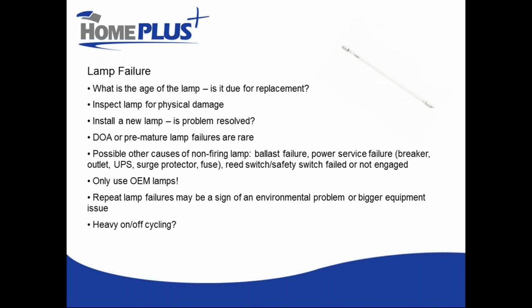Repeated lamp failures could also be a sign of a failing ballast or bigger equipment problem related to the power supply, especially if that's causing very heavy on-off cycling of the lamp. UV lamps prefer to just turn on and stay on continuously. Most of the wear and tear happens starting and stopping them. So I know there are some water systems that batch process their water. They turn their system on for an hour a day, fill a big reservoir, shut it all off, including their UV system, and then turn it on the next morning and repeat. That's really, really hard on the UV lamps and will often result in premature lamp wear. So that's something to be aware of if you're operating your system in that manner.